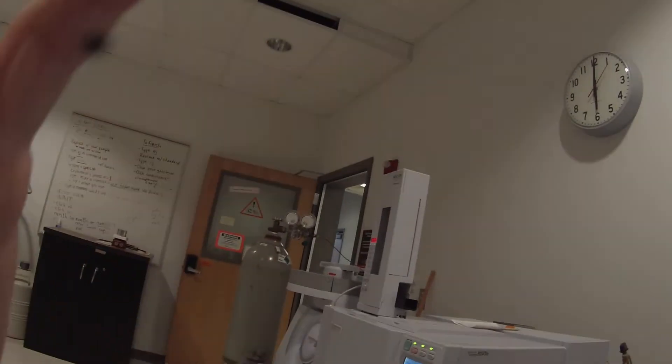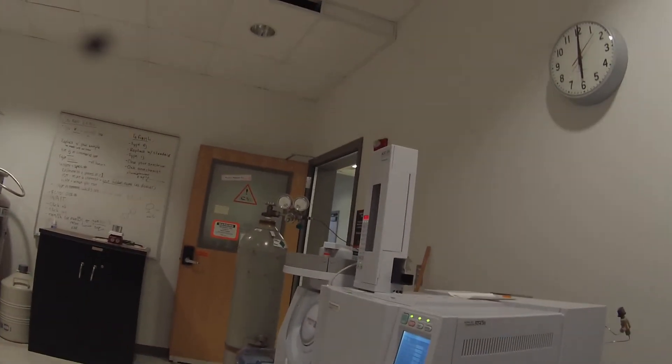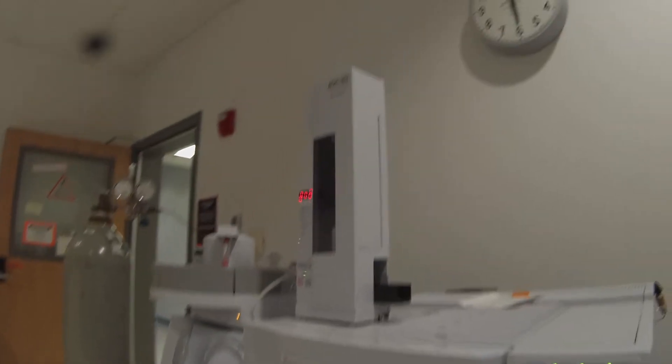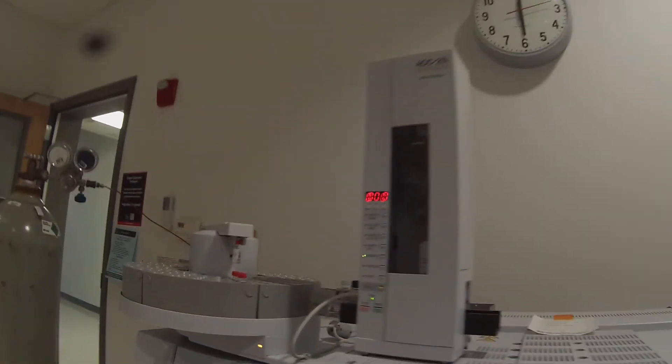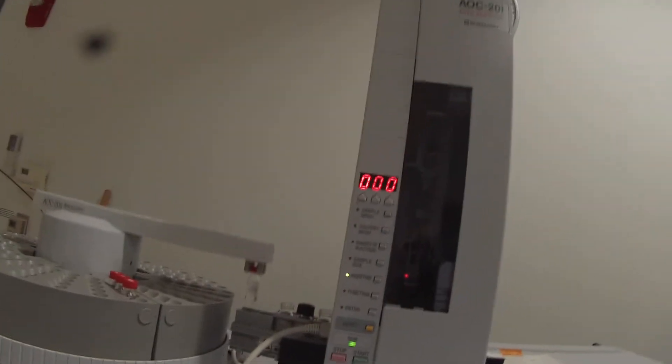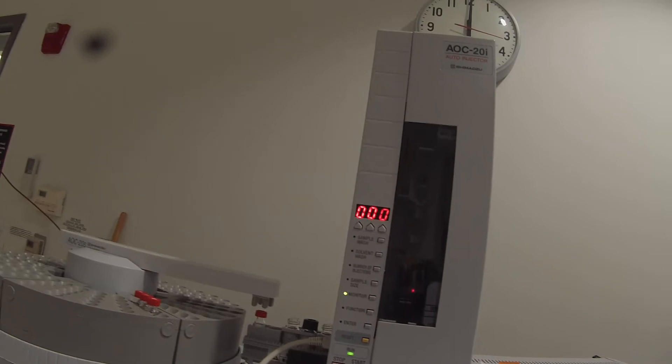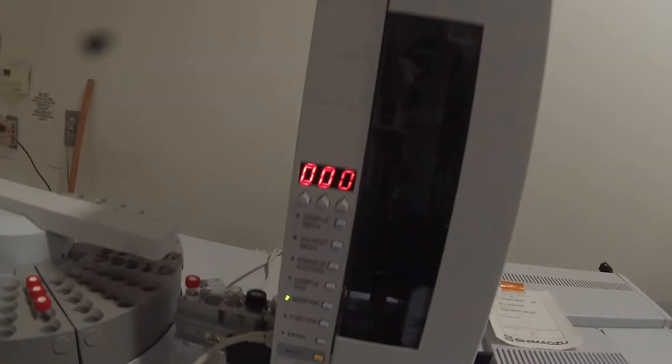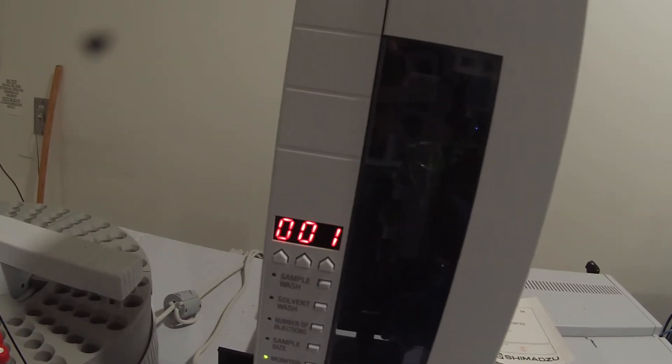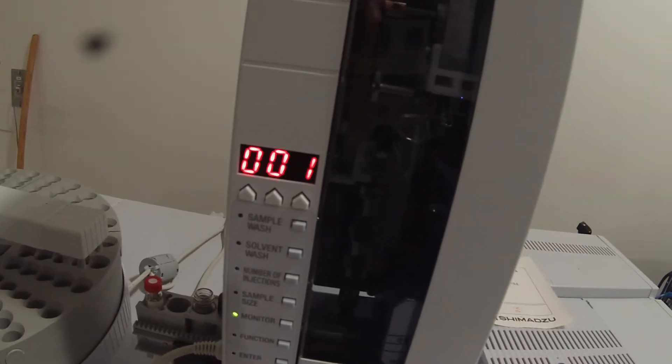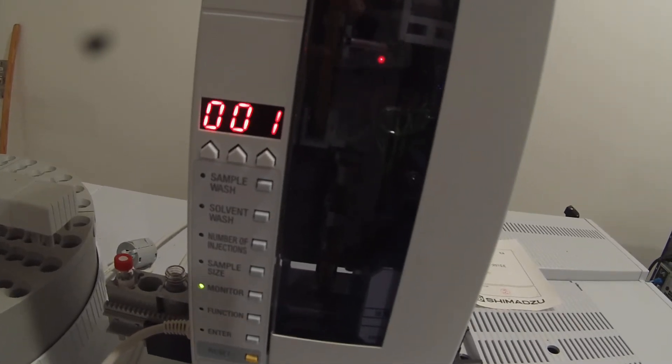We have our batch file running. The syringe is where the auto sampler is grabbing the first sample. Grabbing that over and then you'll see that the syringe will go to that first solvent where we filled it with methanol and start washing the syringe with methanol. So we'll let that go.